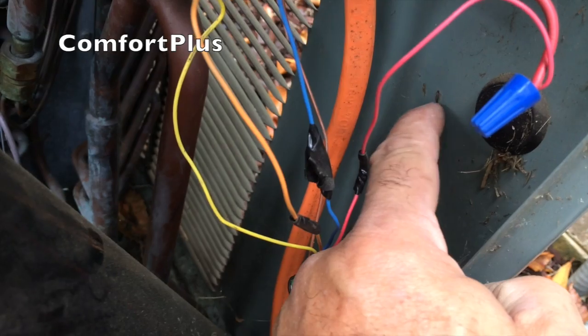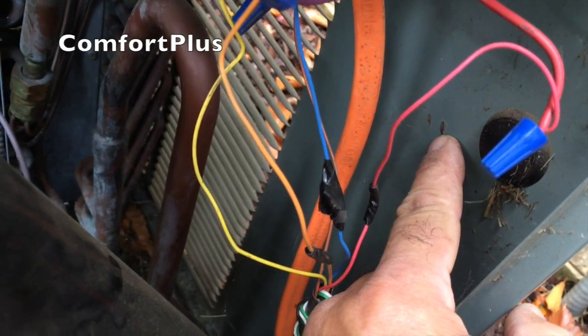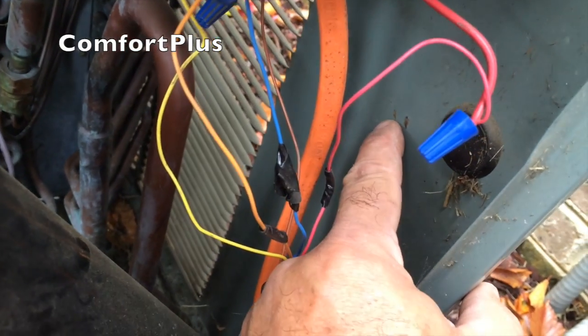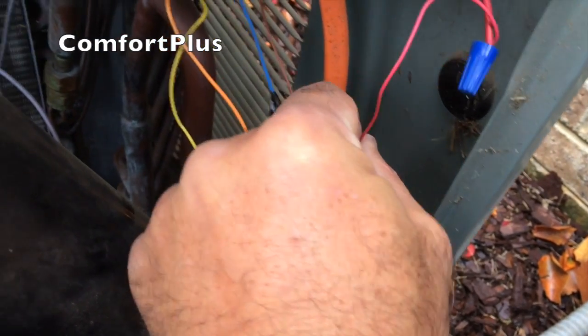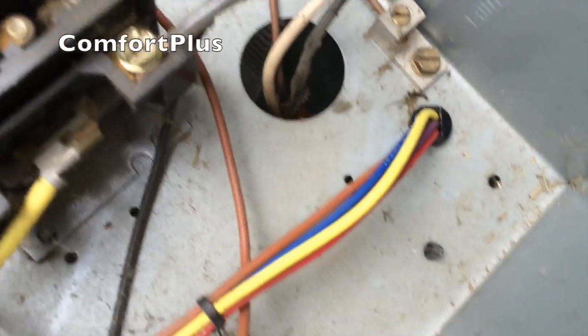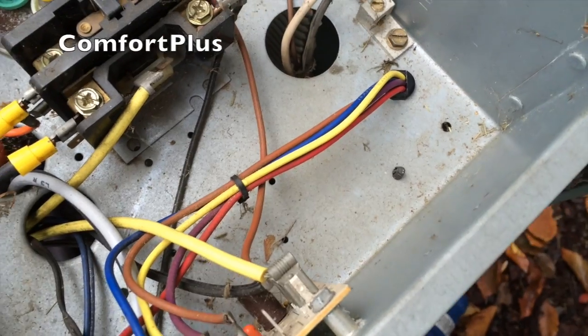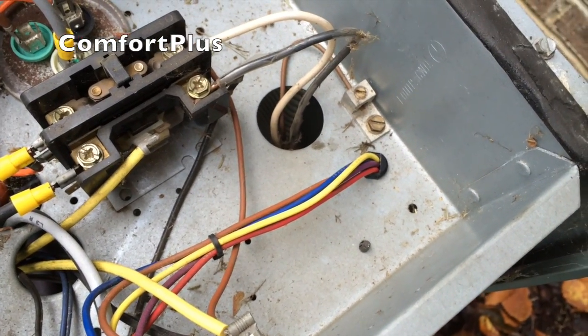You can see there was actually two rubs. I'd say this was the blue reversing valve wire, and this was probably the red wire that was almost rubbed through right here. It was real close if it wasn't all the way rubbed through. So I got my grommet back in. I'm going to button it up and check it out.